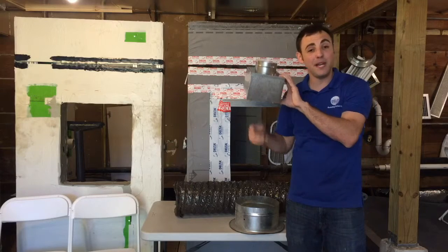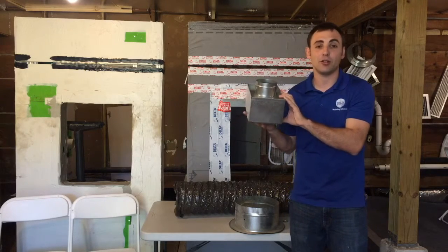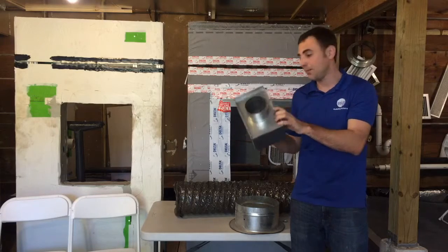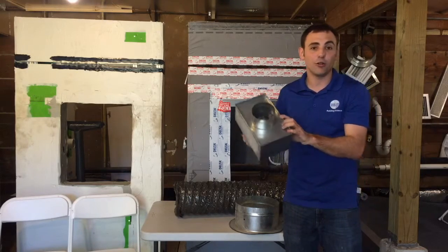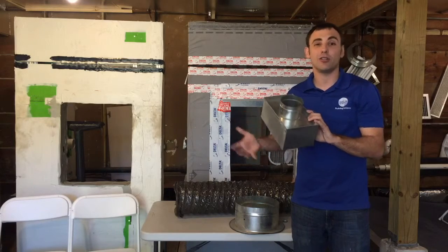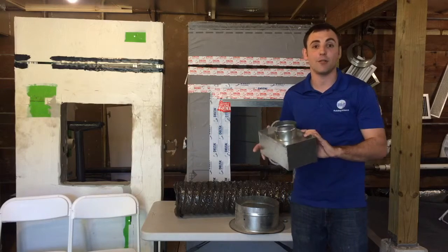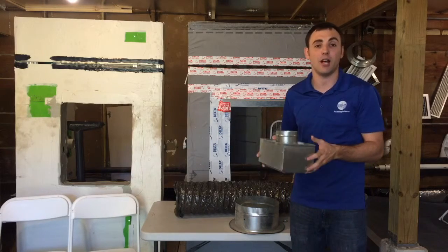So the air speed is going to increase, but the volume of air really isn't going to increase that much. And so when you increase the speed like that, when it passes by a metal louvered grill or something like that, it could start whistling. It could create all sorts of noise issues or make it sound like it's cooler than it actually is in that room just because of increasing the velocity.